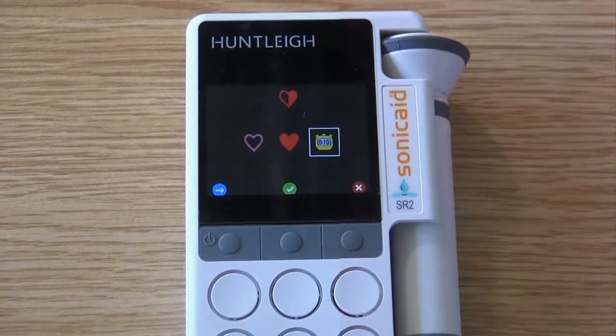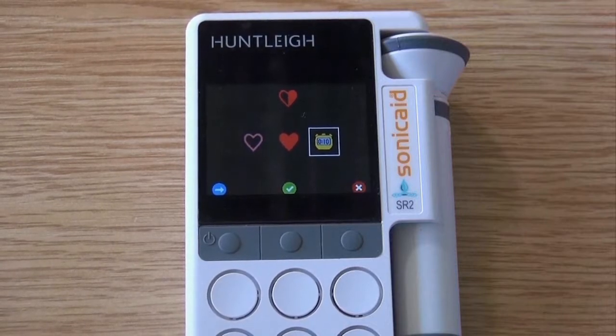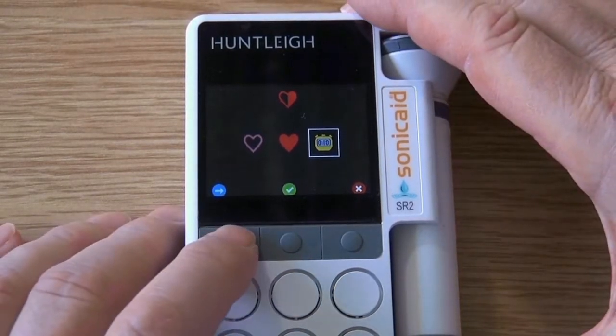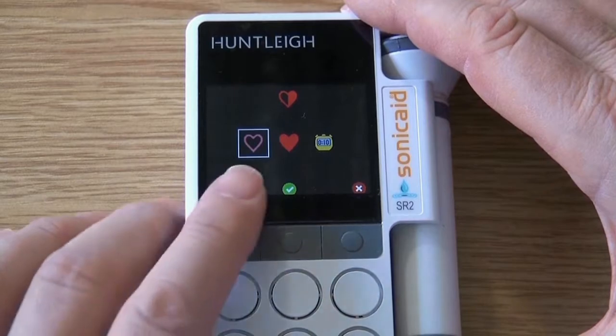The stopwatch mode is used mainly for noisy or very low-level signals that can be heard by ear but that the Doppler cannot calculate a rate from. Read the user manual for details on this mode. Press the green tick to accept.